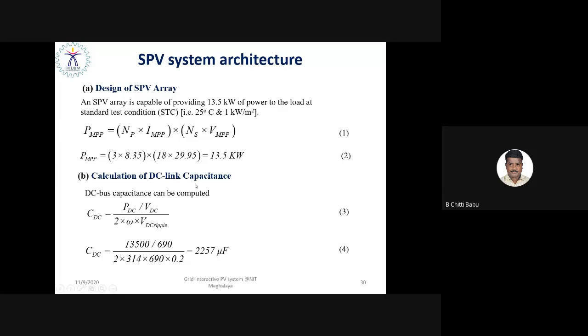So the calculation of the DC link capacitor is very much essential, as you are transferring 13.5 kilowatts of solar PV power to the DC link. Still, the DC link voltage has been designed at 690 volt, so that you are able to invert 690 volt DC into 415 volt line to line. The DC link voltage should always have a higher rating than the peak line to line three phase AC voltage, as we employ the pulse width modulation technique.